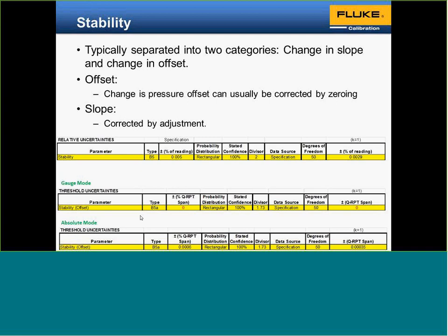A change from the previous presentation: I added the gauge and absolute threshold uncertainty. For gauge mode the uncertainty is 0, because every time you zero the instrument when it's vented, you remove the zero drift. For absolute mode, it depends on how often you're zeroing a 100 kilopascal sensor or a lower range sensor. So you include the uncertainty from the barometer that you're using, and you include the stability, which could be different. You might have one A700K that drifts within its specifications every time, and you might have one that doesn't drift at all. So it's good to measure your instruments so you know their performance.